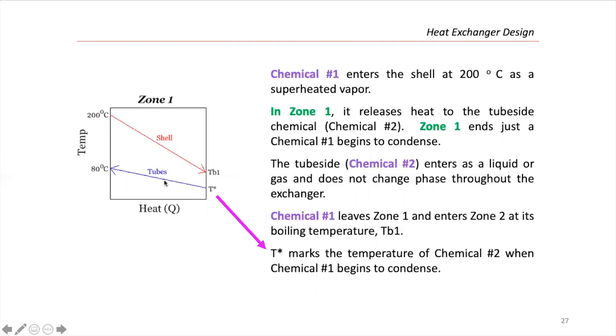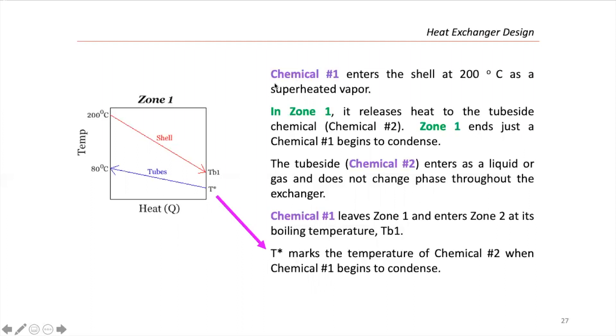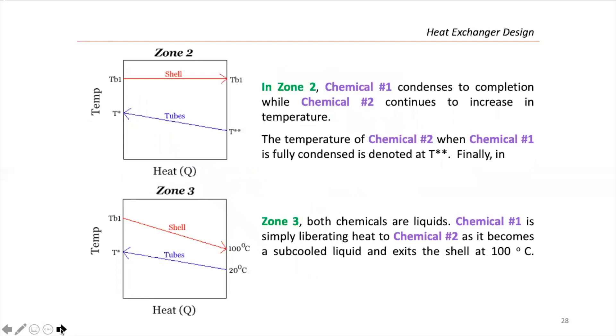Here I'm dividing into three zones. In zone one, chemical one enters the shell at 200°C as a superheated vapor and releases heat to the tube-side fluid (chemical two). Zone one ends just as chemical one begins to condense. The tube-side chemical two enters as a liquid or gas and does not change phase throughout the heat exchanger. Chemical one leaves zone one and enters zone two at its boiling temperature. T* marks the temperature of chemical two when chemical one begins to condensate.